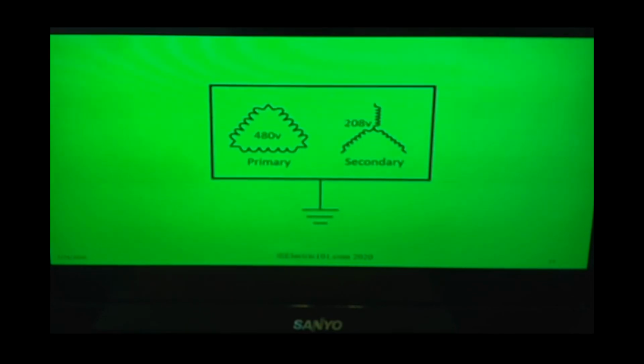Now, the most common type of transformer system you're going to see is what's called a delta Y system. This is the most common you'll see in industry. Okay, primary voltage can be anything. I have 480 as an example. Secondary voltage is typically going to be 208. All the primary windings are connected together in delta. All the secondary windings are connected as Y.